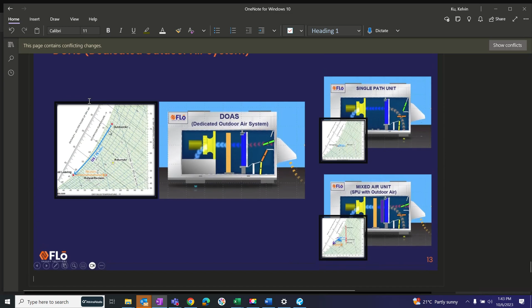And by doing so, we get passive reheat of our dehumidified air, and we get free cooling of our return air. Because the byproduct of a dehumidification coil is cold, dry air. So instead of reheating it and dumping it into the store, why don't I use that cold air to cool my recirculation air? And so that's what we do. That is the core thing about what is special about our product. This is patented technology. It's very simple in concept, but very powerful in its ability to do things. And so we really minimize our need for reheat, and we get all of this extra free cooling.